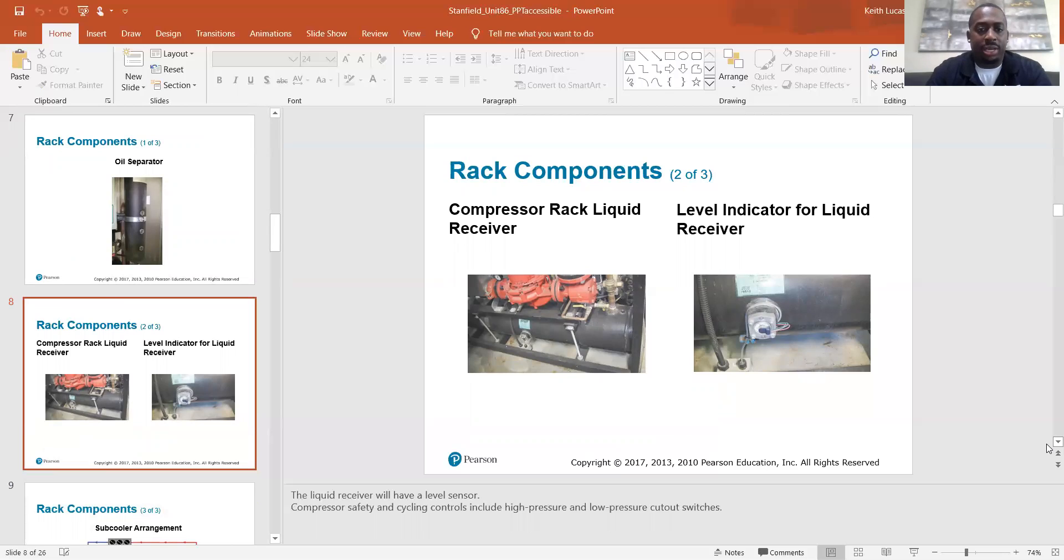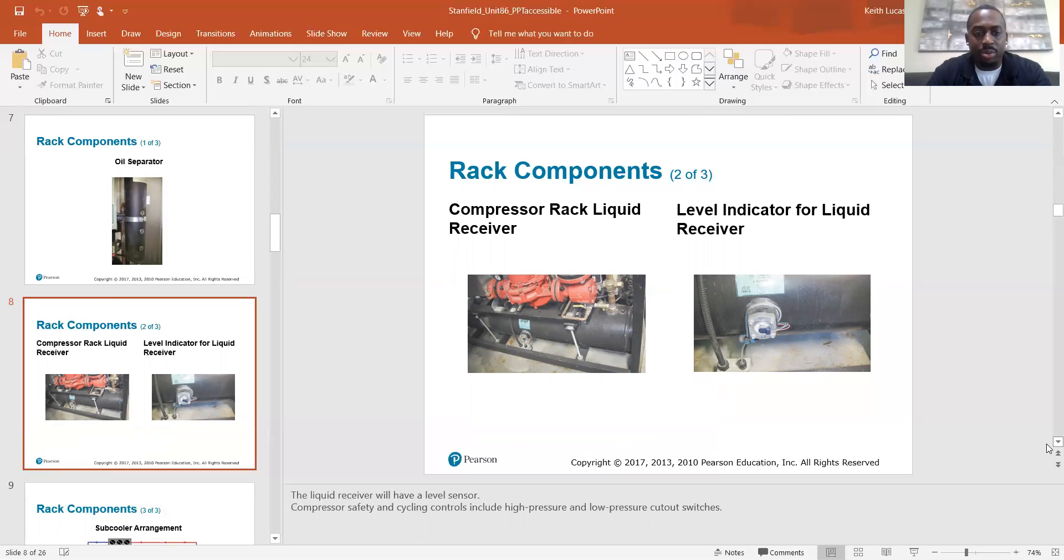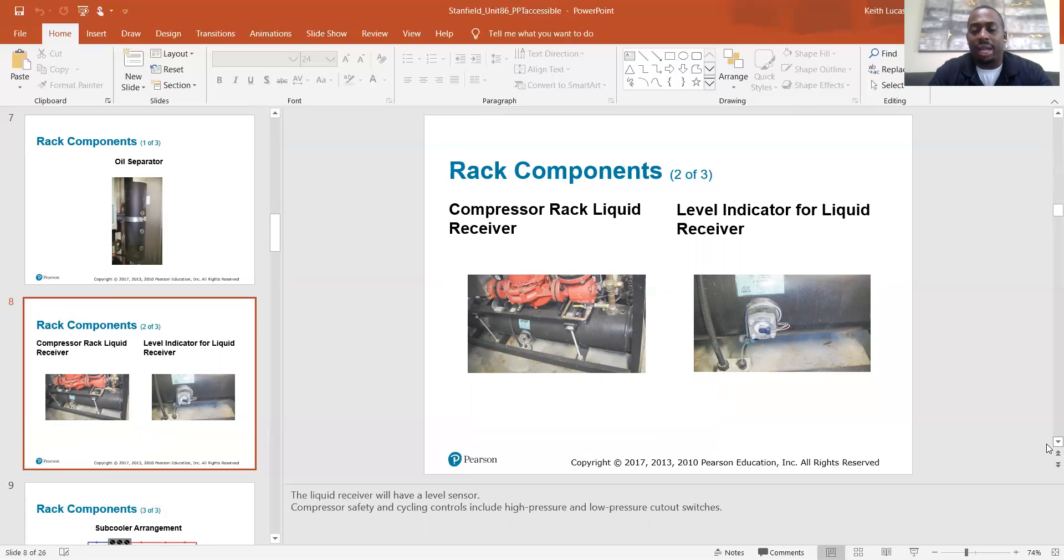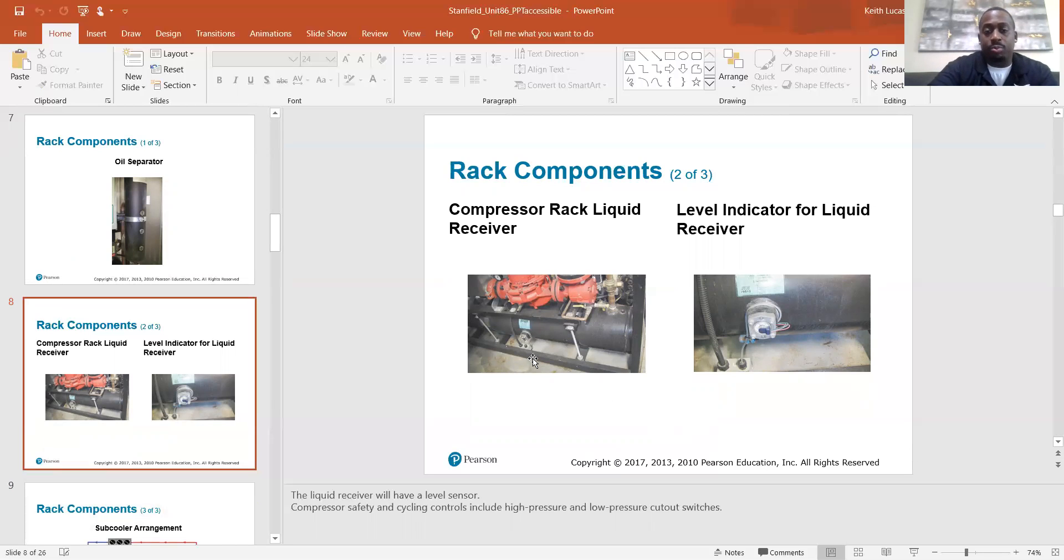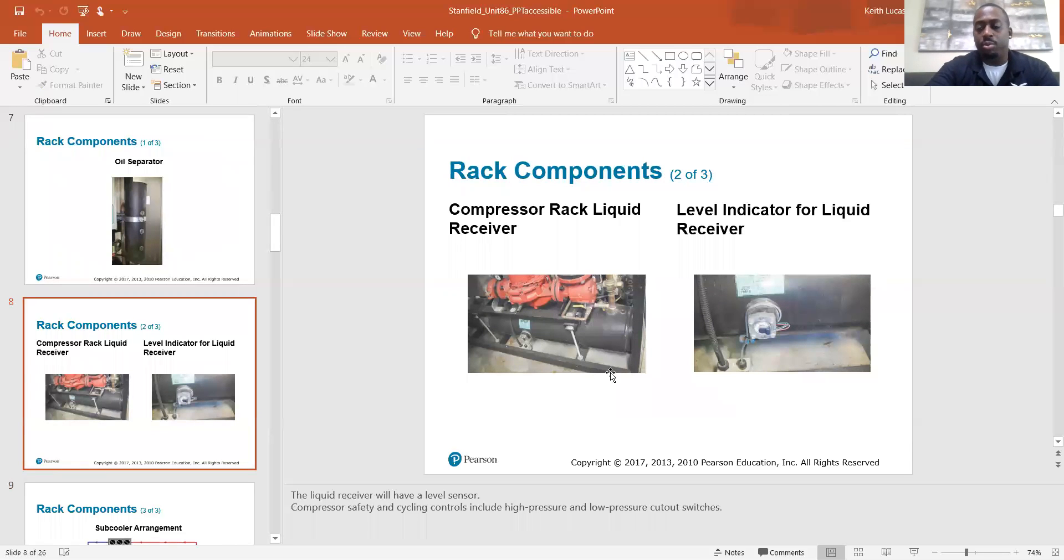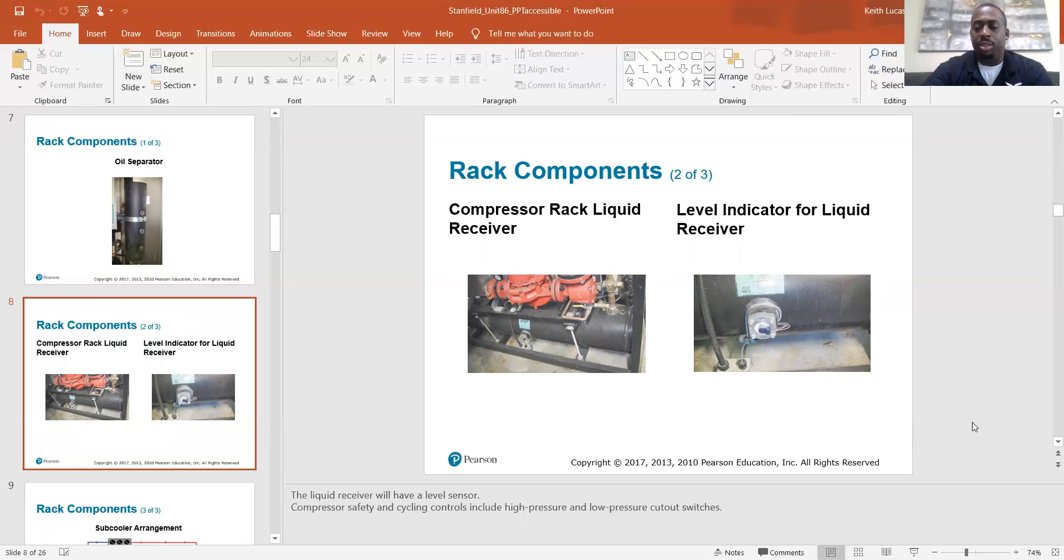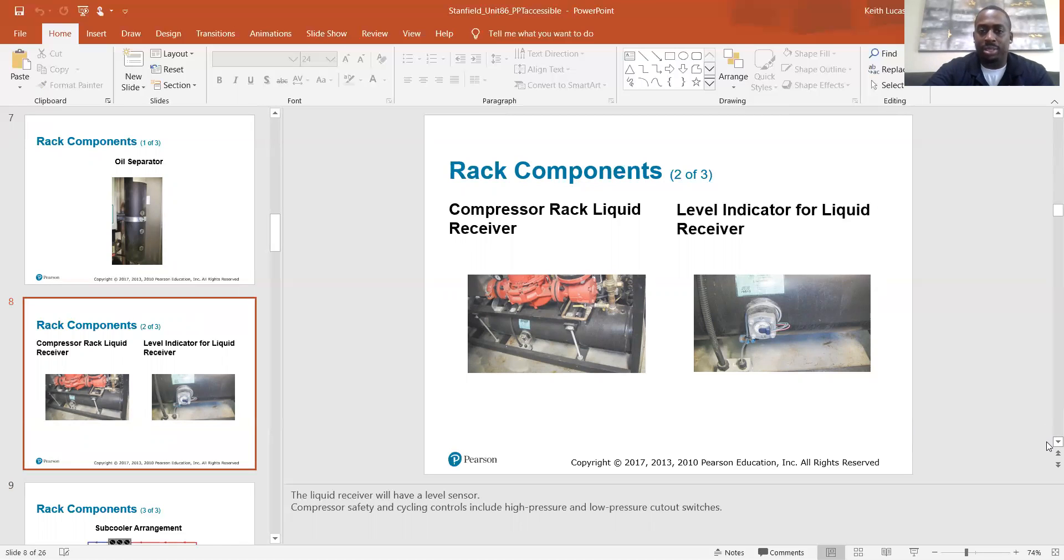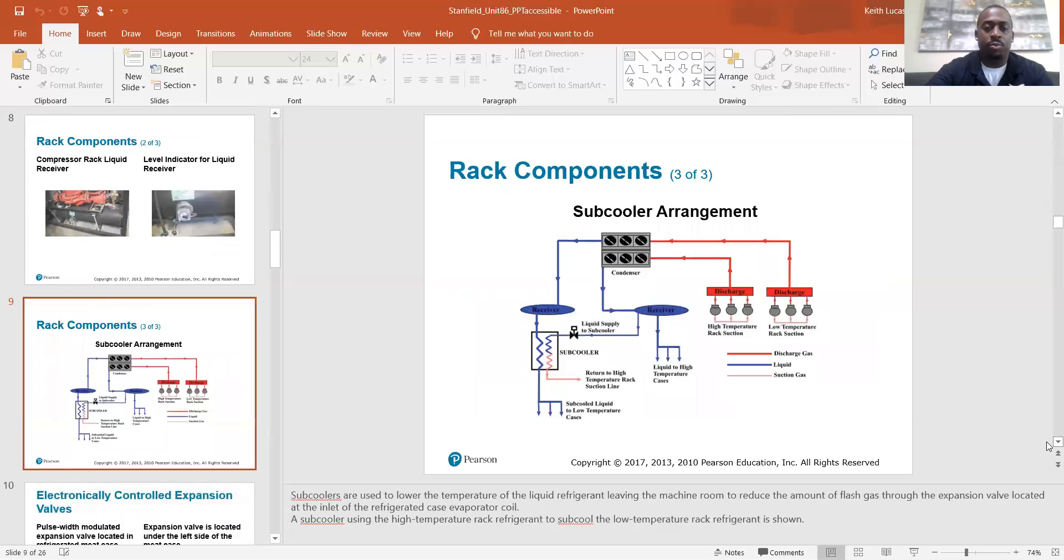Rack components. Some more components, you have your liquid receiver and your level indicator for your liquid receiver. So the liquid receiver will have a level sensor. Compressor safety and cycling controls include high pressure and low pressure cutout switches. So just a quick review on the receiver, we all know that the receiver is where it stores liquid refrigerant when it's not necessary, when it's not being used, like with low cooling demand. It won't need all of this liquid. So that is basically the storage tank for when you don't need all of the liquid.